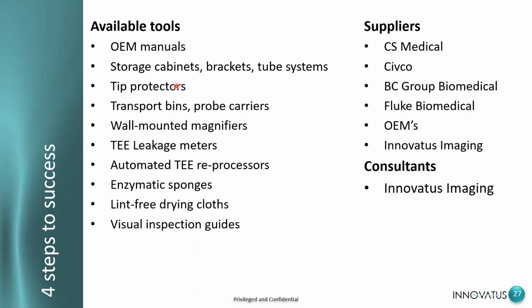We'll talk about tip protectors in a little bit. Hypercritical there. Transport bins and probe carriers. Those are hypercritical. Wall-mounted magnifiers. Don't see many people using those, although they would tremendously reduce the amount of TEE damage if people were to use them. Leakage meters. TEE leakage testing is required if you are accredited by the IAC, the Intersocietal Accreditation Commission. If you're not accredited by the IAC, it is still highly recommended for two reasons. One is for patient safety, of course. That's always our first and foremost concern. But also a leakage test is a wonderful indicator of a probe that has a breach, that has some type of trauma where liquid can get in and can start penetrating the probe, and that's where we get into catastrophic damage. So leakage testing should be done on every single TEE probe for those reasons.